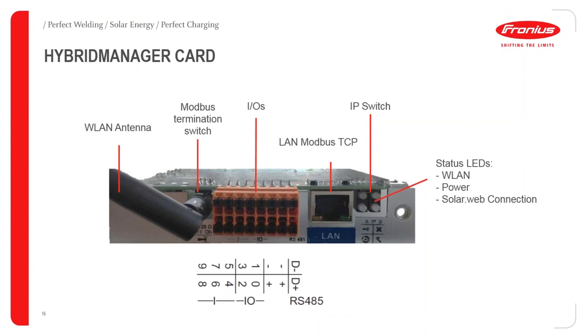Okay, just to give you a bit more of a close-up of the hybrid manager there, you can see on the left you've got your Wi-Fi antenna like usual. There's the Modbus termination switch, so depending on where the inverter or the battery or the meter sits in the chain, always the first and the last component needs to have a 120 ohm termination resistor there. So if the hybrid inverter is the first one or the last one, so not in the middle, then that little 120 ohm resistor is already built into the card, but as a switch, so you can turn it on and off. It's just above where the antenna is, this tiny microscopic little black switch, which you need to switch to either on or off depending on the situation you're in.